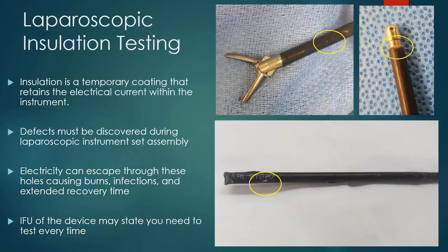What I'm seeing now when I go to facilities is that every care is taken every step of the way, and Seth will be talking about that in more detail regarding transport and testing of your instruments. But what I see is all this care is taken with the devices, and then they're put in with metal instrumentation, which Seth will talk about, and then I see damage from there. So you can test for damage and replace items, but then they could be re-damaged in the tray once it's wrapped and sterilized.